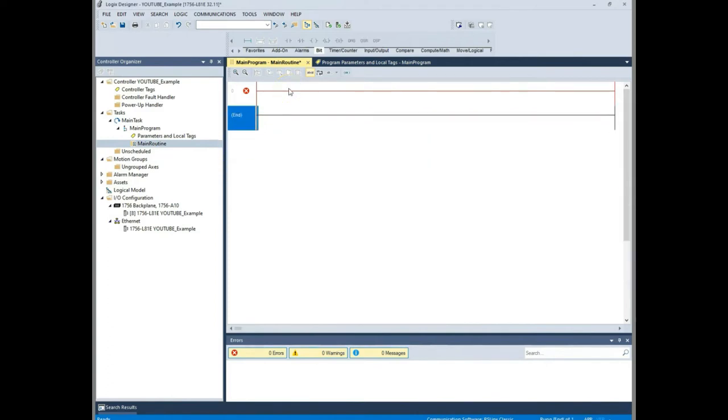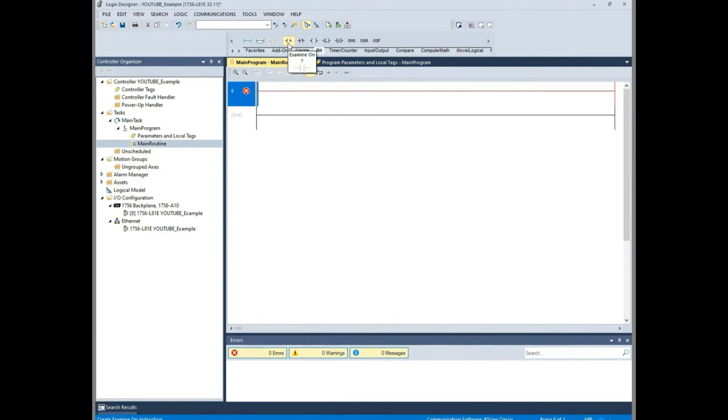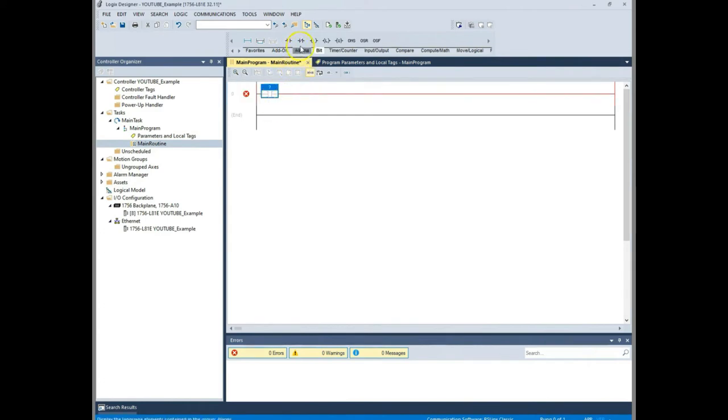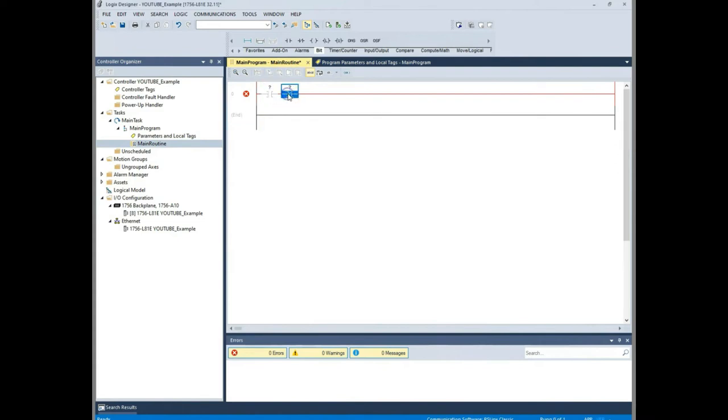So let's start with rung 0 here. Remember we're going to create that same motor starter circuit that we used before. But we're going to assume that our stop is normally open and our start is normally open. So in order to do this we need to start by using our XIC here and we can add this in a couple different ways. You click the rung. I can just simply come up here and click on the XIC to add it to my rung there. Or we're going to use an XIO for my stop. You can select this, hold your mouse down and drag it down to wherever you want it. And you'll see that green circle light up to where you want to place it at. So we're going to place ours there. So now I have an XIC and an XIO.